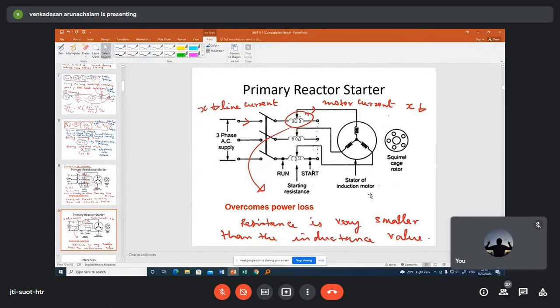Of course, every inductance will have a very minimum resistance, but the resistance value is very small compared to the inductance value in the primary reactor starter. So because of this, the copper loss will be minimum when compared to the primary resistance starter. In these two starters, any doubts anybody is having?